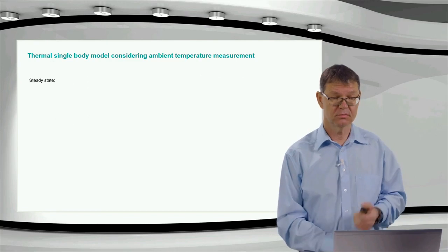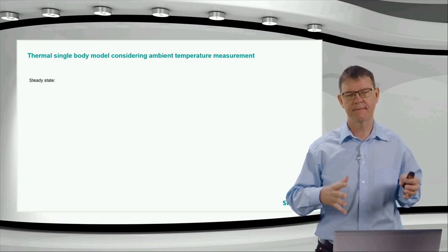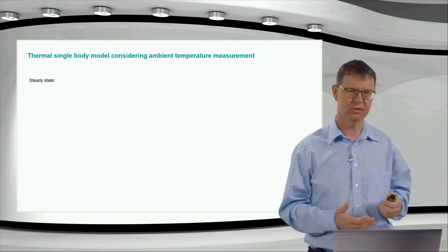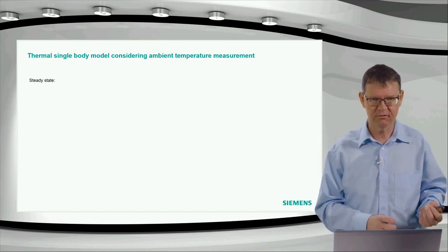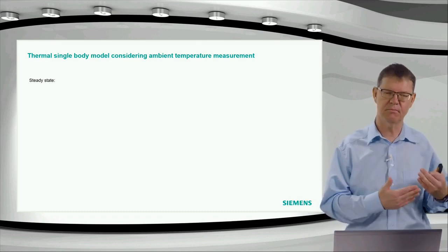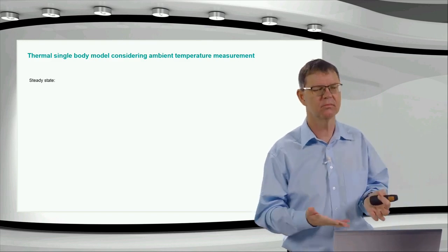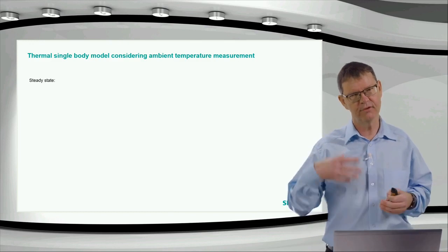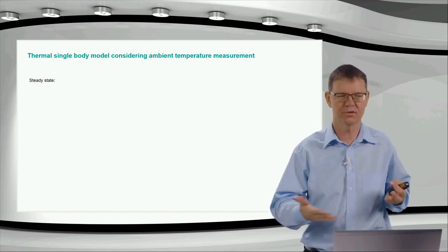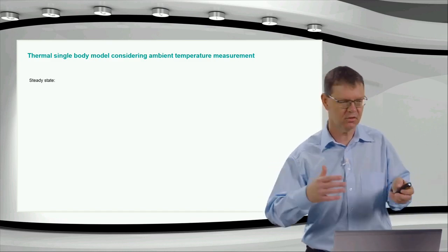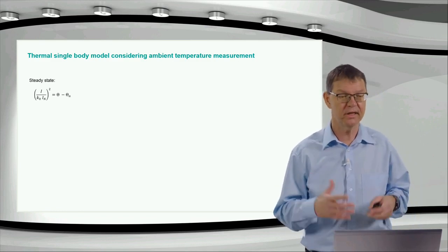Okay, I would like to give you some advice, let's talk about some situations. One is if we consider the ambient temperature. This is not done very often with a sensor. We have the possibility to add a sensor and measure the ambient temperature and bring this into this calculation. Or I have another ambient temperature, permanently higher than the 40 degrees. Then I also need to know what to set now. Do I need to modify the K factor, or what shall I do? Therefore, here are some considerations which guide you to the right conclusion at the end.